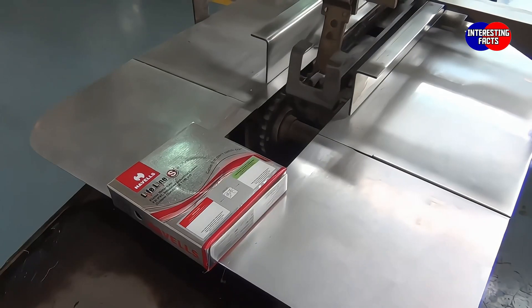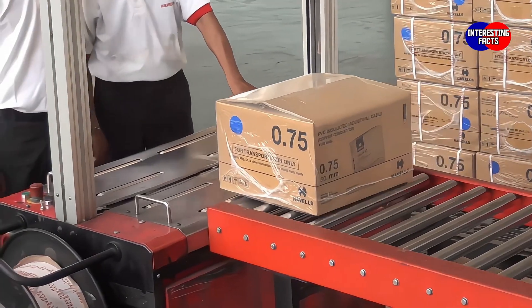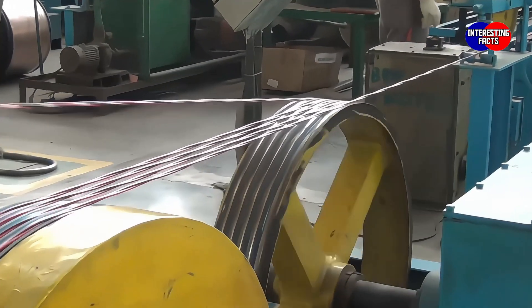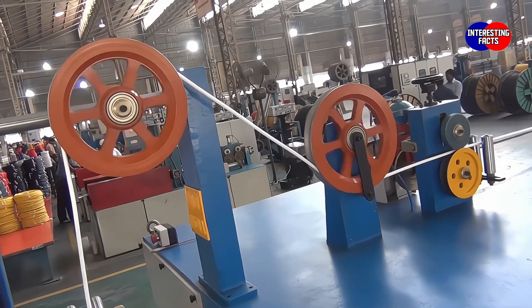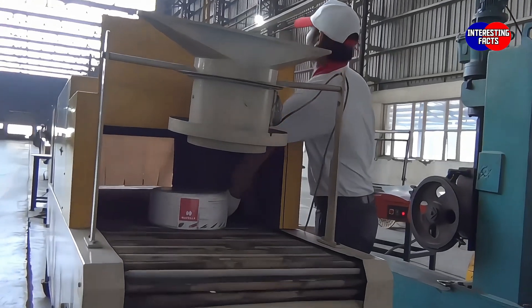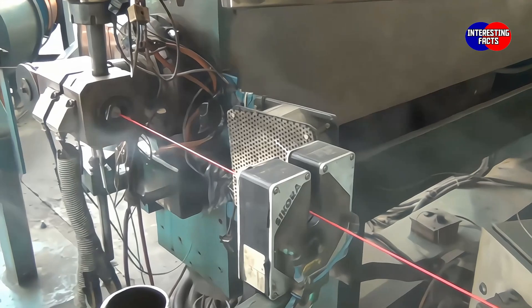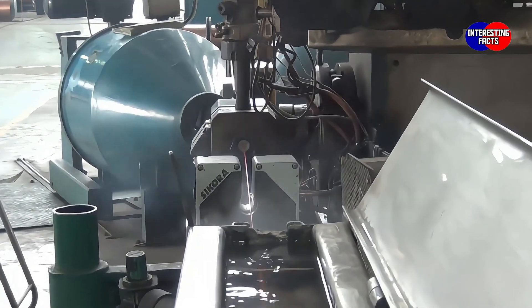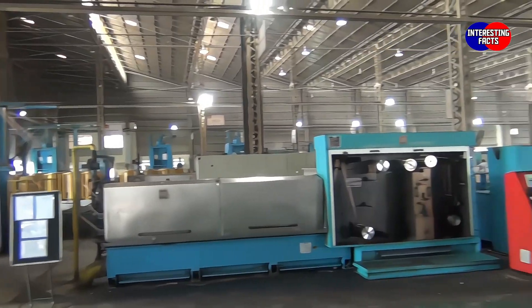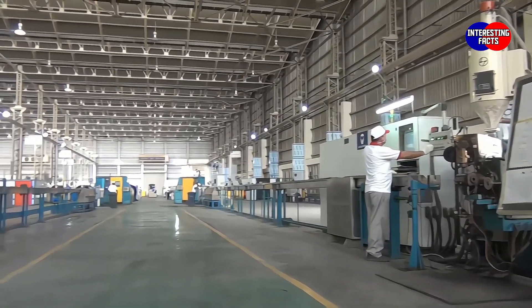Havells wires and flexible cables are packed with safe, moisture-free and good-looking packing to deliver the material in good condition to customers. Multi-core flexible cables are twisted and sheathed with white PVC granules to obtain the final product. The white flexible cable is coiled on modern coiling machines with length-measuring units, and each coil is packed with a suitable label and shrink-wrapped with a polyethylene layer for safe and moisture-free binding. The PVC insulation is done in a double-layer process — the first layer with virgin PVC for insulation, and an outer layer, commonly called skin, with color PVC. This is done to avoid the adverse effect of color pigment on insulation resistance, as virgin PVC insulation has very good insulation resistance.